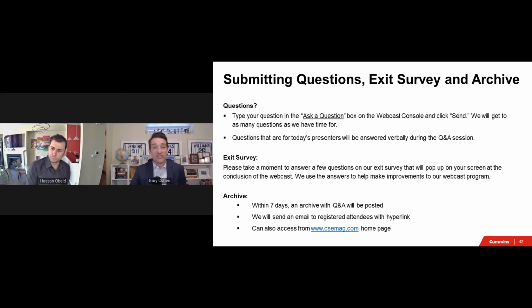Sounds good. Just a few minutes left here. Let's go with, how do you ground paralleled systems? Okay, so that could take us an entire day. Maybe a bigger question than we have time for. Well, maybe quickly, I'll make it simple for a parallel system. For low voltage, you have to bring the neutral from the generators into the distribution board, and there you'll connect, hopefully, the neutral to ground bond. For medium voltage, what we typically see is neutral grounding resistors are used, and you typically have one per generator. That's how it's typically done with a parallel system.